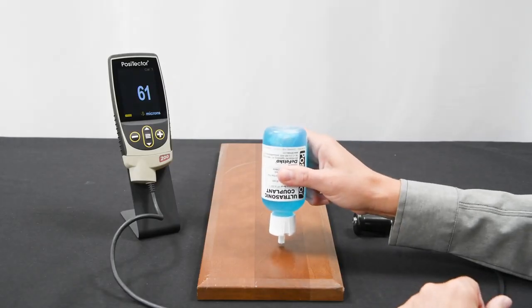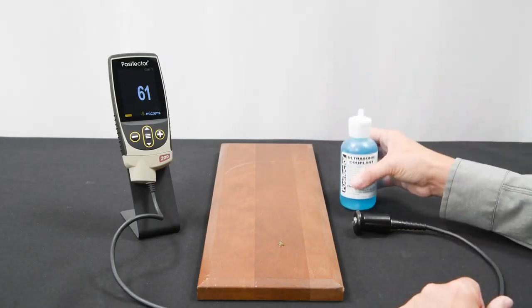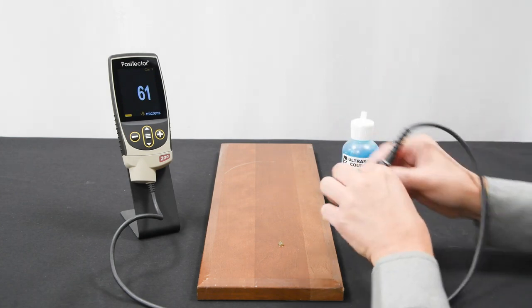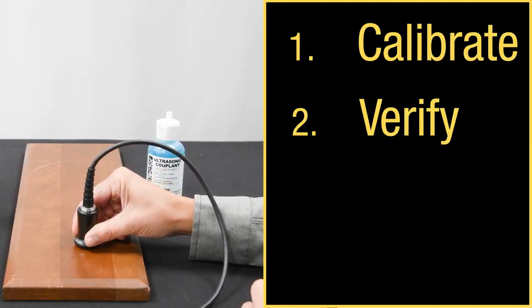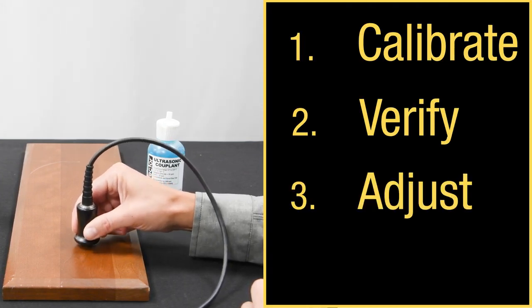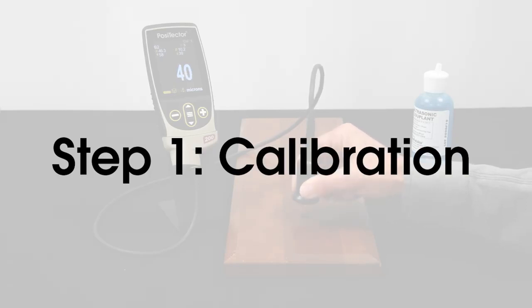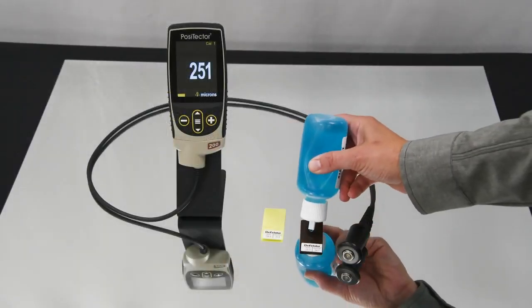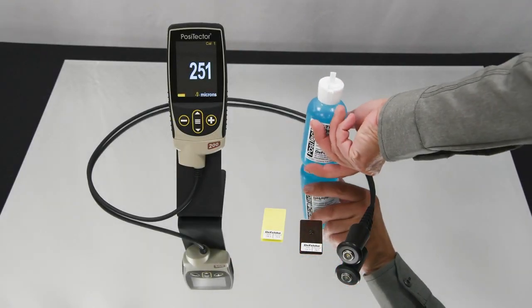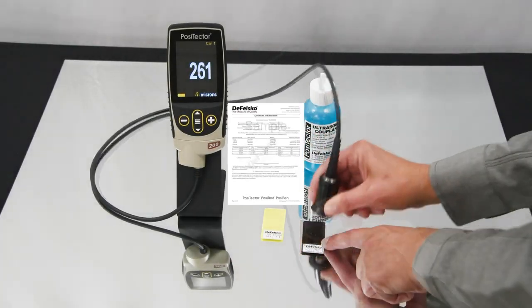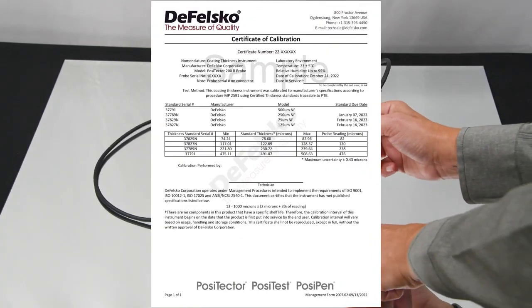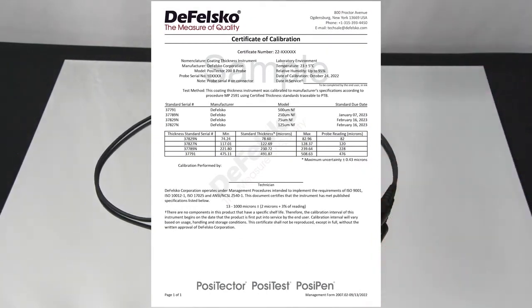Measuring with any Positector 200 probe is simple. Most standards describe the following 4 operational steps: calibrate, verify, adjust, and measure. Calibration is performed by DeFelsko or an accredited laboratory and involves taking measurements on traceable standards throughout the range of the probe under controlled conditions. The result is a long-form certificate of calibration, which is included at no charge with every Positector 200.